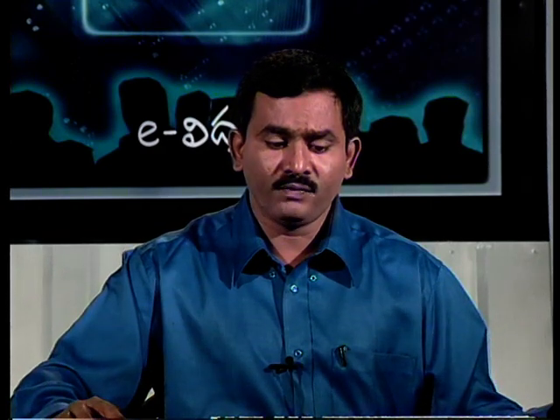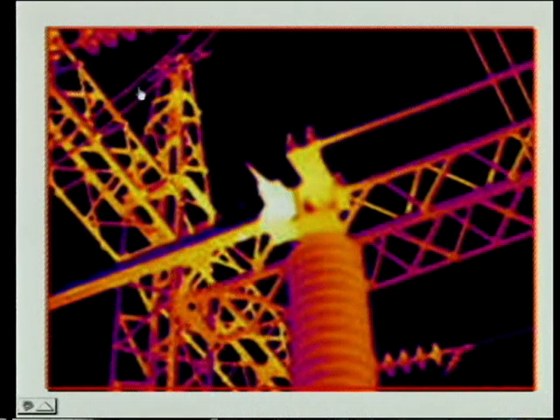Here you can see the figure. Here is the bus. If the current capacity is more, then we can use two conductors, double conductors. Sometimes we can use hollow conductors or tube, galvanized tube. This is one example of a bus bar system. You can see how the bus bar is connected to different loads and to the CT and PT by using clamps. Here is the bus bar. It is connected through a jumper through clamps. It is an example of a bus bar system.